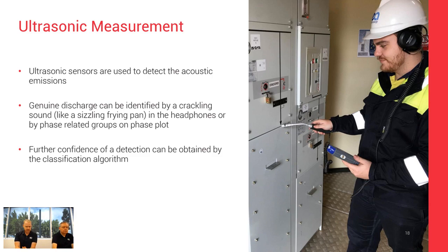Here we have one of our engineers, it's Thomas again. He's got his headphones on and he's using the UltraTEV Plus 2 with an airborne microphone, and what he's effectively trying to do is listen into all the different high voltage chambers at a switchboard or at a ring main unit, and listen into each chamber to effectively test for sound. Once we get the sound, there we go, across to the next one.